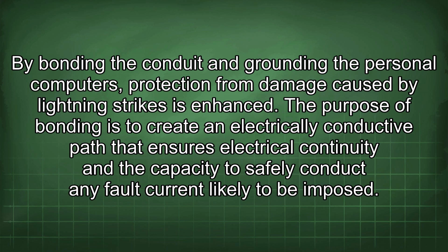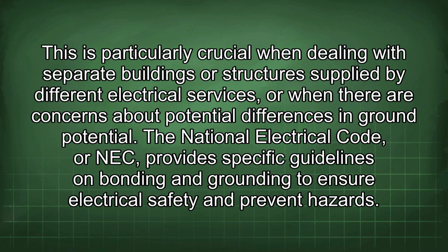The purpose of bonding is to create an electrically conductive path that ensures electrical continuity and the capacity to safely conduct any fault current likely to be imposed. This is particularly crucial when dealing with separate buildings or structures supplied by different electrical services, or when there are concerns about potential differences in ground potential.